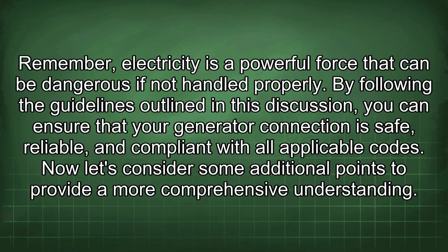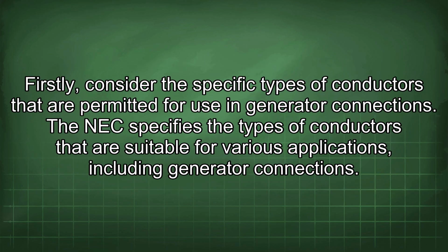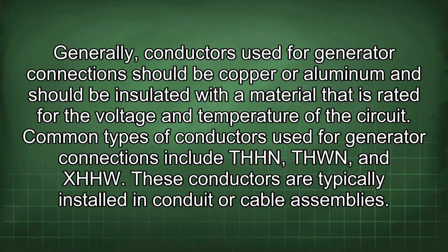Now let's consider some additional points to provide a more comprehensive understanding. Firstly, consider the specific types of conductors that are permitted for use in generator connections. The NEC specifies the types of conductors that are suitable for various applications, including generator connections. Generally, conductors used for generator connections should be copper or aluminum and should be insulated with a material that is rated for the voltage and temperature of the circuit.